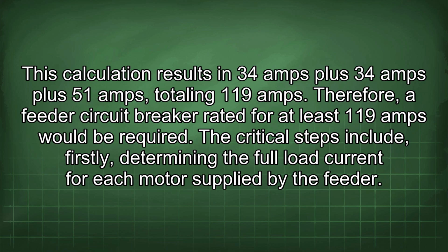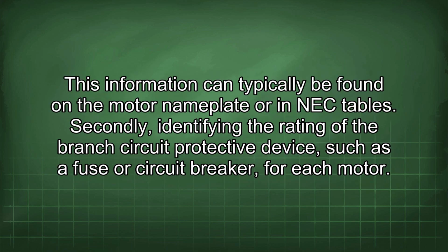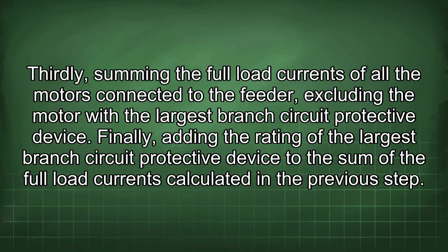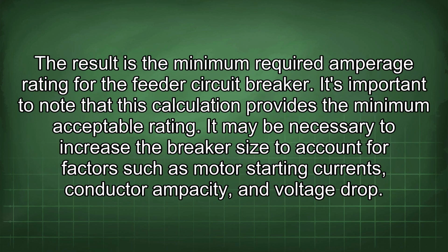The critical steps include, firstly, determining the full load current for each motor supplied by the feeder. This information can typically be found on the motor nameplate or in NEC tables. Secondly, identifying the rating of the branch circuit protective device, such as a fuse or circuit breaker, for each motor. Thirdly, summing the full load currents of all the motors connected to the feeder, excluding the motor with the largest branch circuit protective device. Finally, adding the rating of the largest branch circuit protective device to the sum of the full load currents calculated in the previous step. The result is the minimum required amperage rating for the feeder circuit breaker.